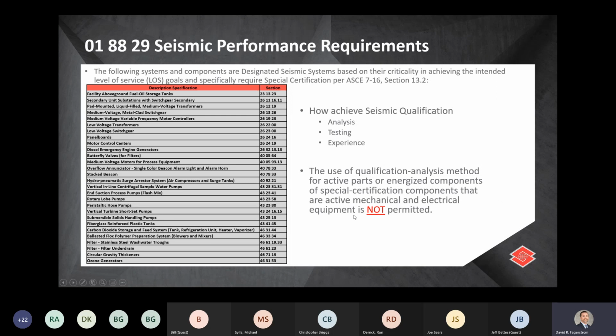The last note, also taken from the spec, states that the use of qualification by analysis method for active parts or energized components of special certification components that are active mechanical and electrical equipment is not permitted. So basically for the process equipment, you cannot use analysis only for determining seismic certification. You need to use a combination of two methods.